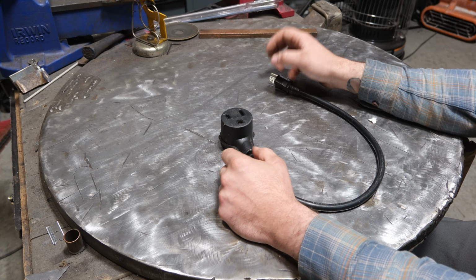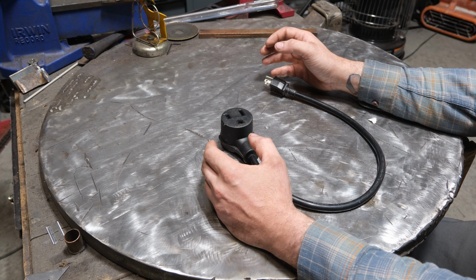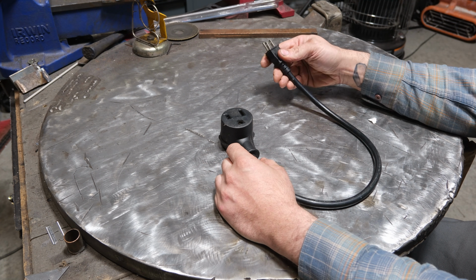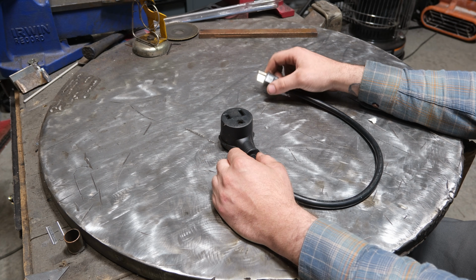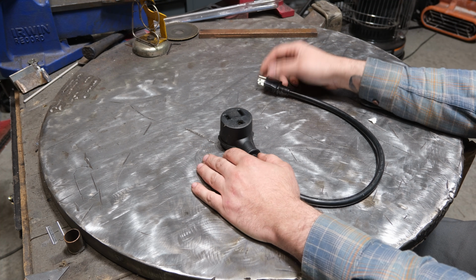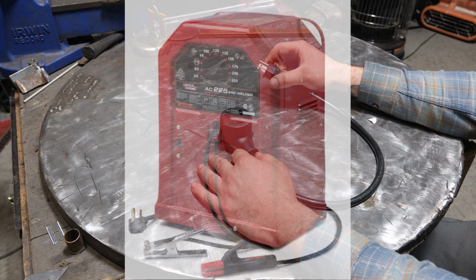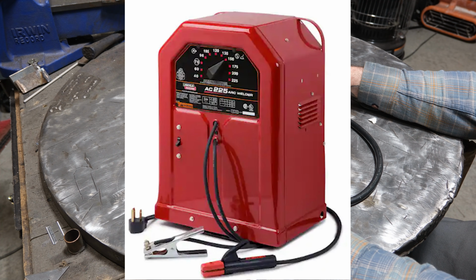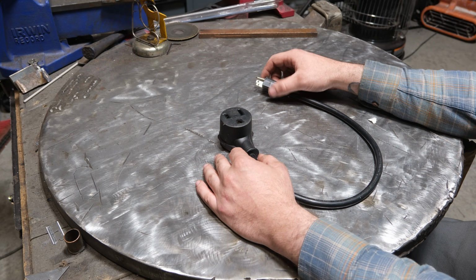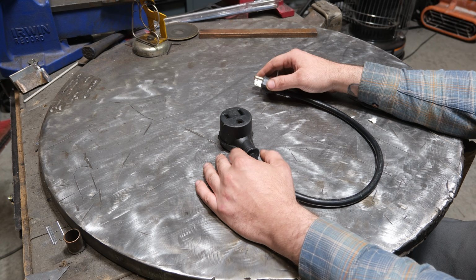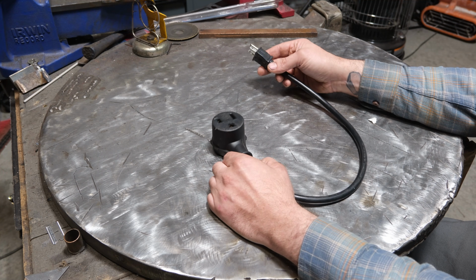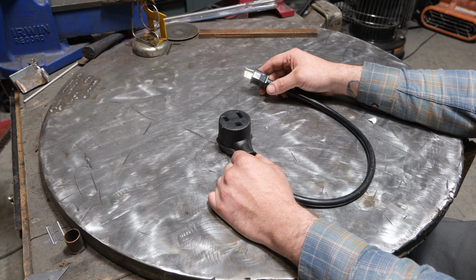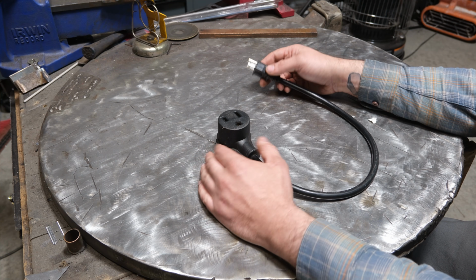With the modern invention of inverter welders, the ability to weld on 120 volts actually became a possibility, versus before when you had your Lincoln Tombstone stick welders and your dial arcs and all those big old clunkers. Running those on 120 volt was completely impractical, because basically all you would get for output is about 30 to 40 amps before it would trip the breaker, and that's basically useless.